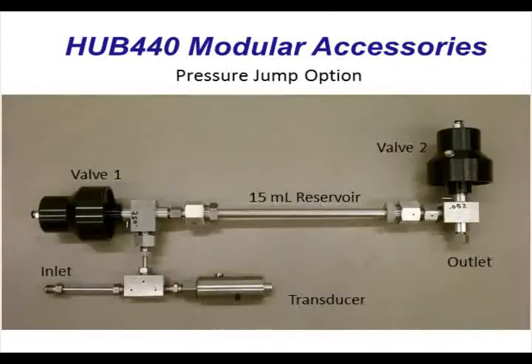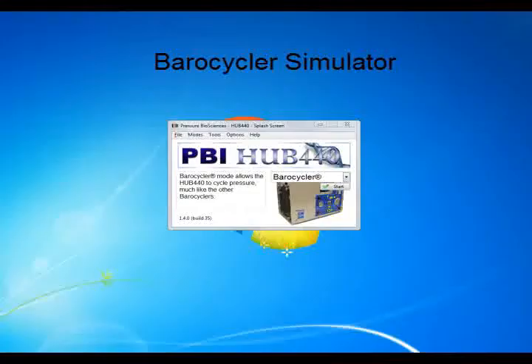A specialized pressure jump option, consisting of a second pressure transducer, two rapid pressure jump valves, and a 15 milliliter reservoir, enables the system to generate changes of pressure both up and down between specified pressure values in under a millisecond. Let's take a look at several examples of how the system operates.